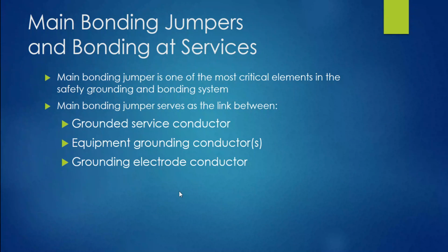Now, main bonding jumpers and bonding at the service. The main bonding jumper is one of the most critical elements in the safety grounding and bonding system. The main bonding jumper serves as a link between the grounded service conductor, the equipment grounding conductor, and the grounding electrode conductor. It's a key component that ties everything together in your panel. We're all familiar with a normal panel in a home: you've got your bus, and your grounded conductor comes in, and it might be black wrapped with white tape, and it goes to the grounded conductor terminal bus. In there, you usually will see a main bonding jumper installed. At that point, you'll also see the bare copper that leaves and goes to a grounding electrode somewhere on that premises, using a grounding electrode conductor. So it brings everything together right there on the same bus.